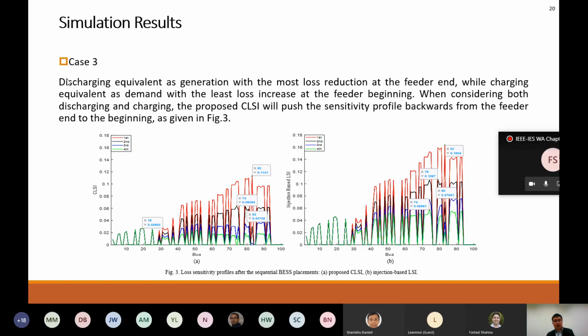Regarding the reason, I have mentioned that discharging means generation, so the most sensitive point is always at the feeder end. But if you consider charging as the demand, the least loss increase is at the feeder beginning. So we consider both charging and discharging, which pushes the sensitivity profile backwards to the very beginning. That's why we have such a solution.